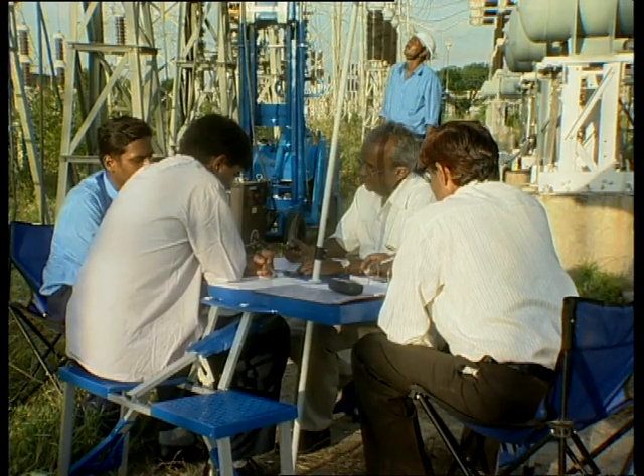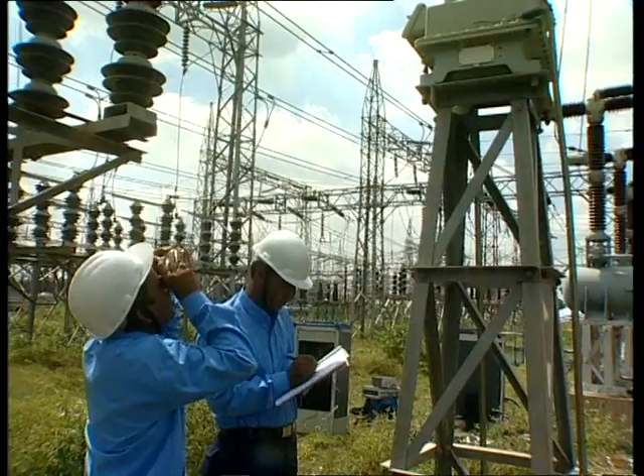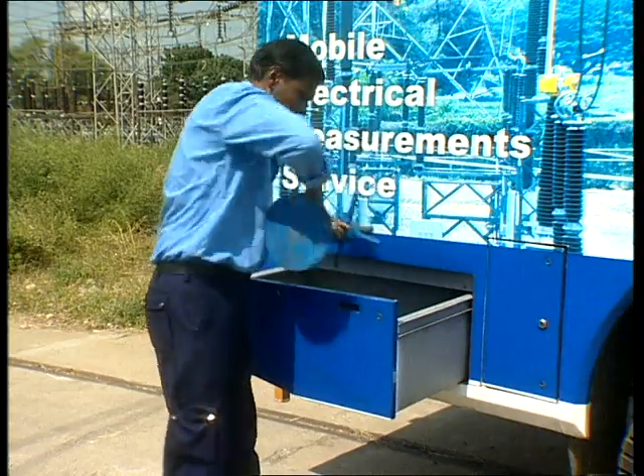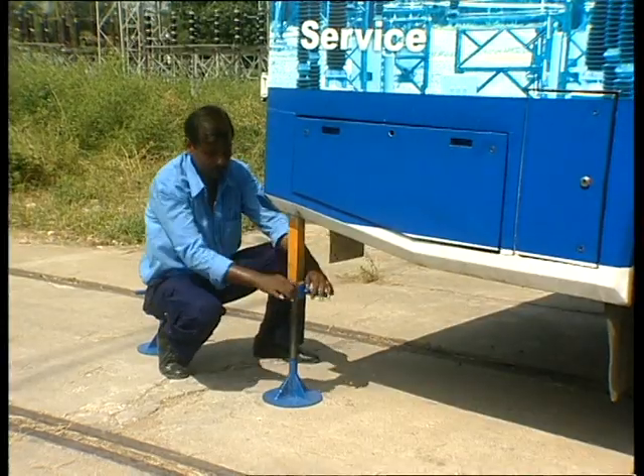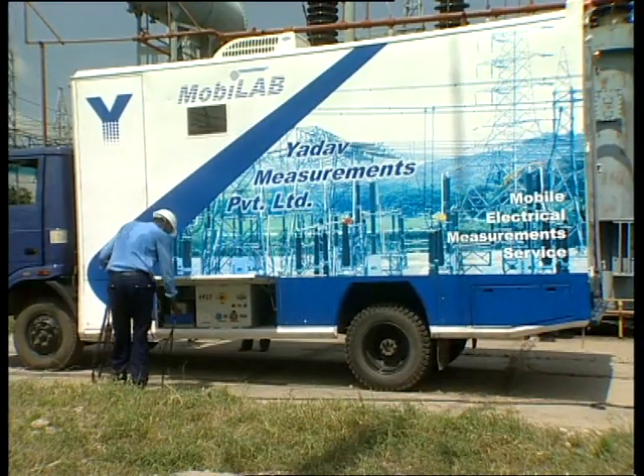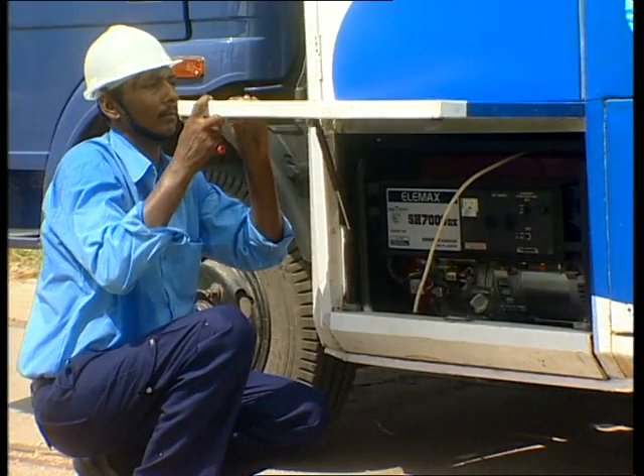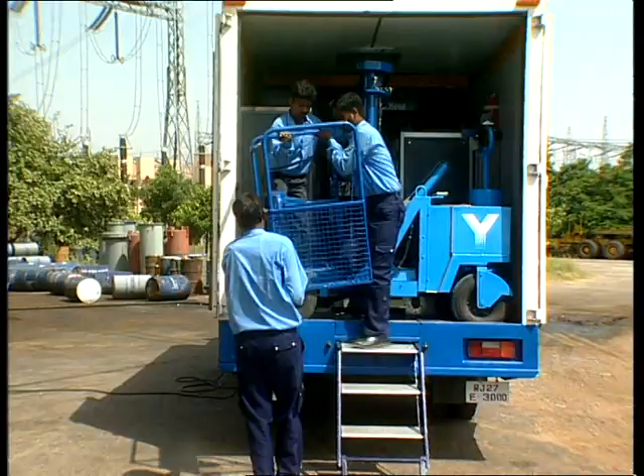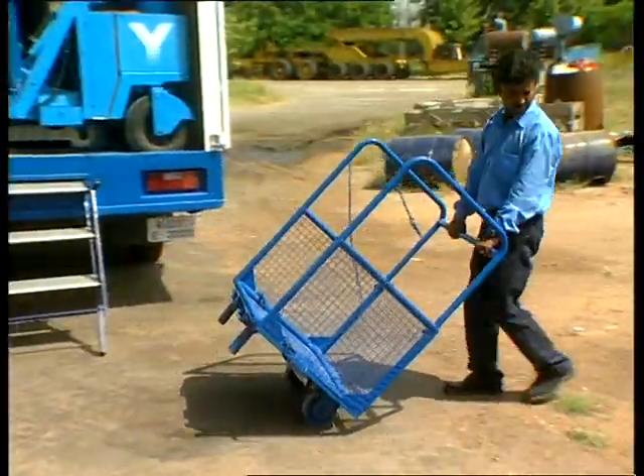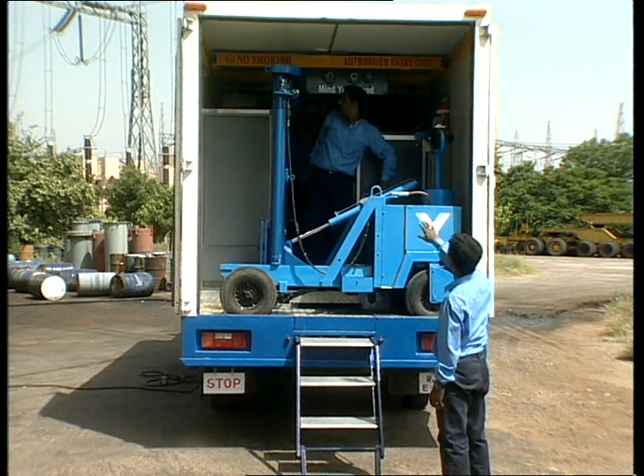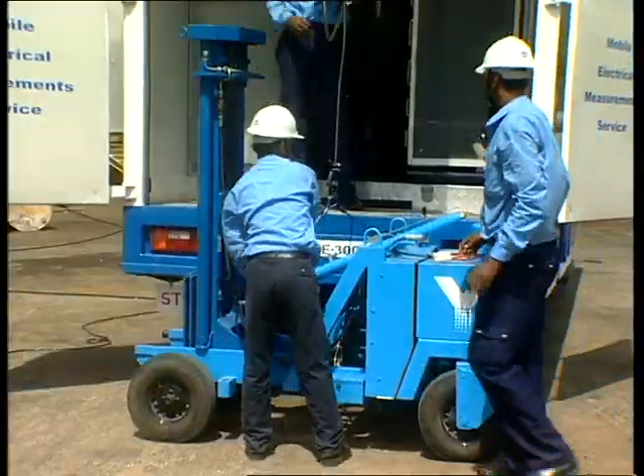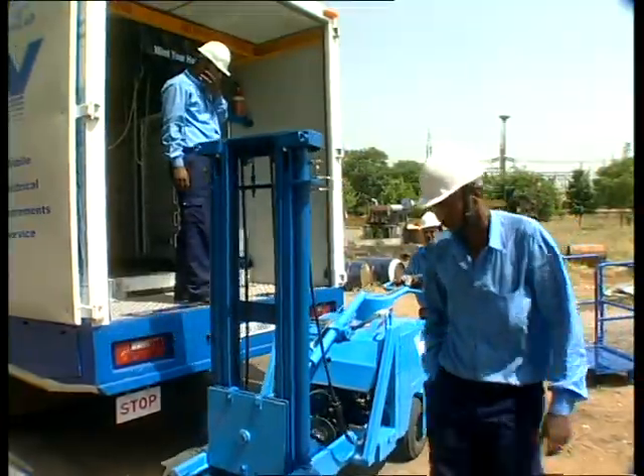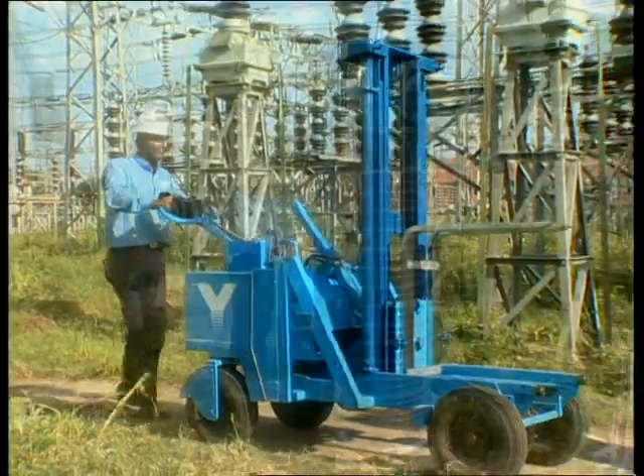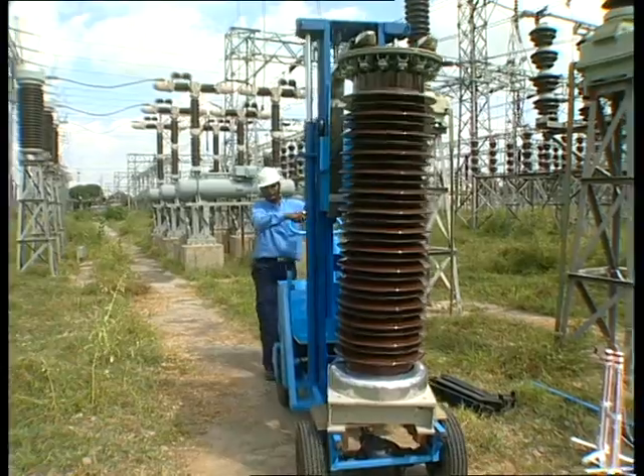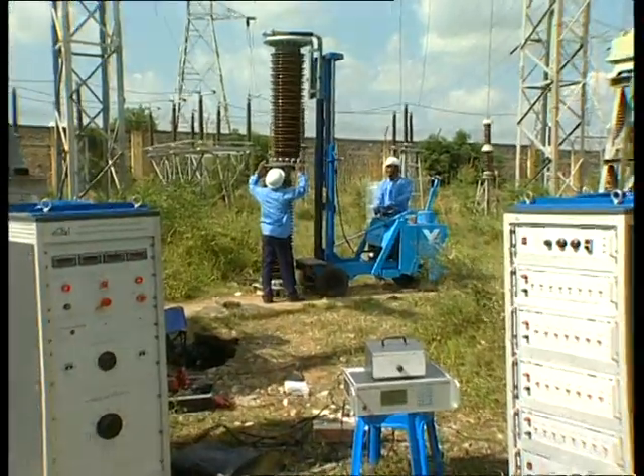Once on site, the MOBILAB crew confirms the work plan and placement of equipment in the substation yard. Having parked MOBILAB at the selected location, it is secured from movement and energized using a power supply derived from the substation. MOBILAB is also equipped with its own backup generator set. Setting up the calibration facility is a matter of moving heavy but sensitive test equipment, a job assisted by purpose-built materials handling equipment carried by MOBILAB. Equipment is unloaded from MOBILAB using a built-in hoist and is transported to the selected location in the substation yard by a custom-built all-terrain material handling vehicle.